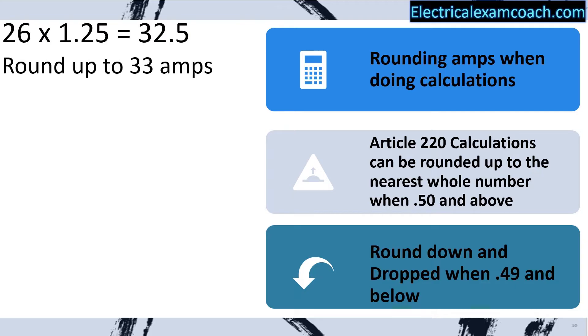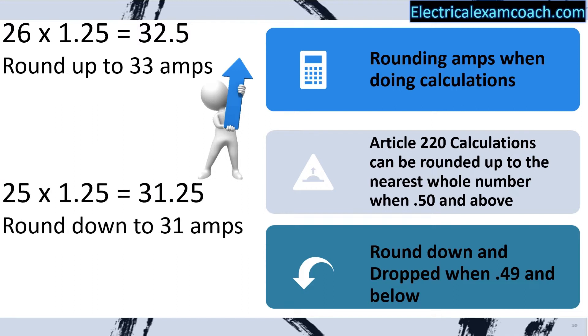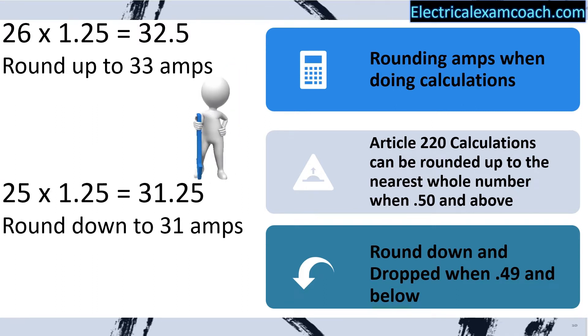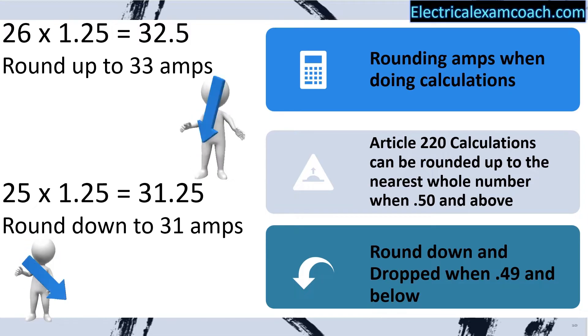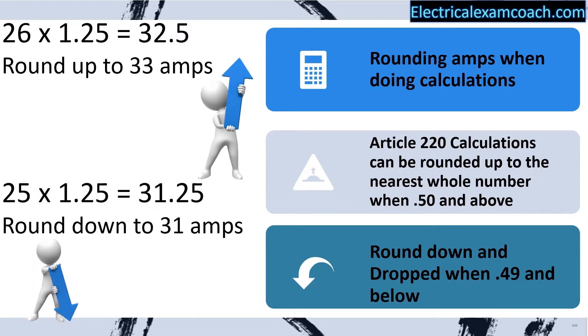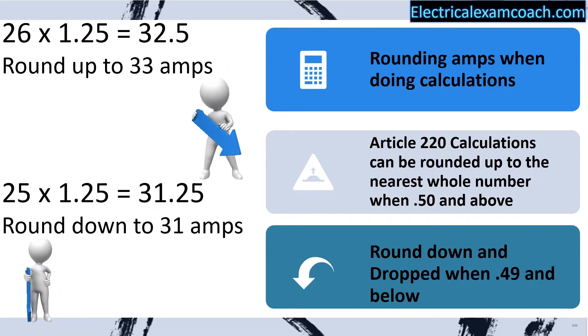Let's imagine we have a scenario of 26 amps, and after we do all of our math, it equals 32.5 amps. In this case, we're gonna round up to 33 amps. Now let's imagine a similar scenario where our answer is 31.25 — that's 0.49 or less, so we are going to round down. And that's how we're gonna deal with all of our numbers in load calculations.